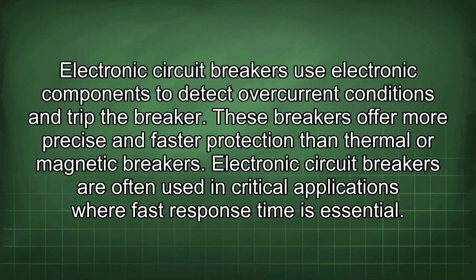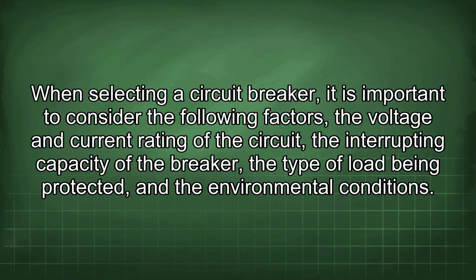Electronic circuit breakers use electronic components to detect overcurrent conditions and trip the breaker. These breakers offer more precise and faster protection than thermal or magnetic breakers. Electronic circuit breakers are often used in critical applications where fast response time is essential. When selecting a circuit breaker, it is important to consider the following factors: the voltage and current rating of the circuit, the interrupting capacity of the breaker, the type of load being protected, and the environmental conditions.